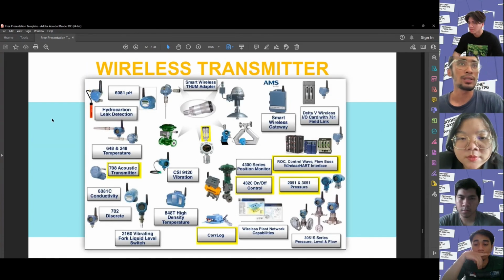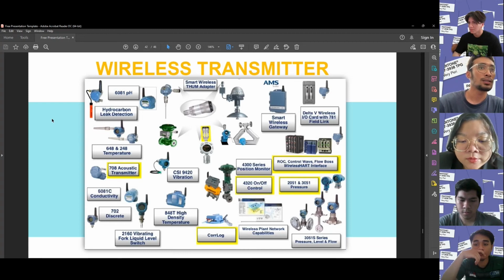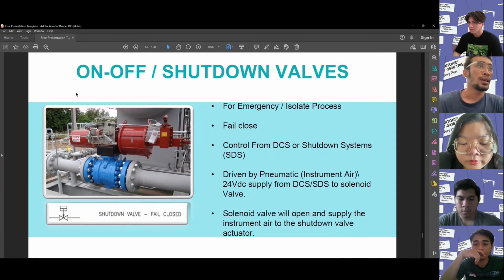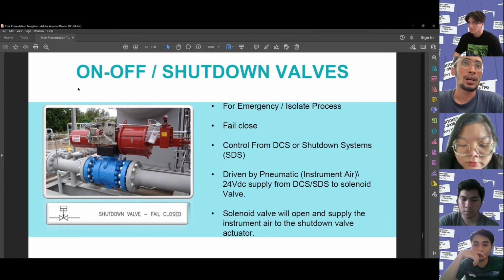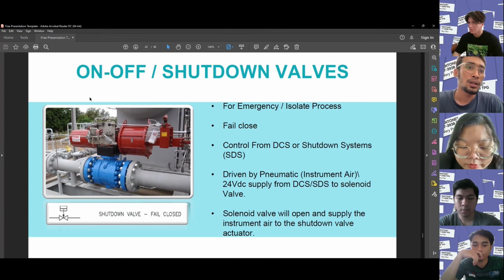The next is the wireless transmitter. And the on-off shutdown valve. First, for emergency and isolating the process, fail close. Control from DCS or shutdown system, driven by pneumatic instrument air or 24 VDC supply from DCS or SDS to the solenoid valve. Last, the solenoid valve will open and supply the instrument air to the shutdown valve actuator.